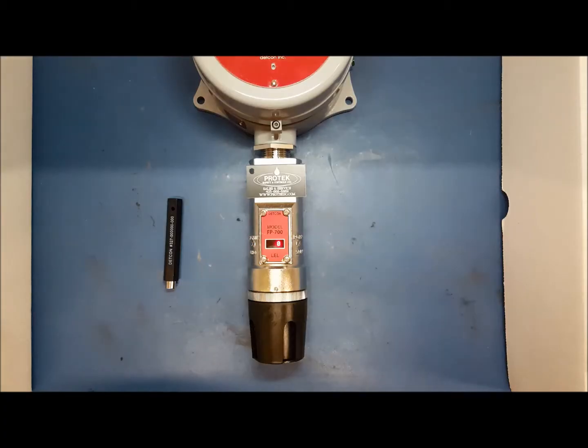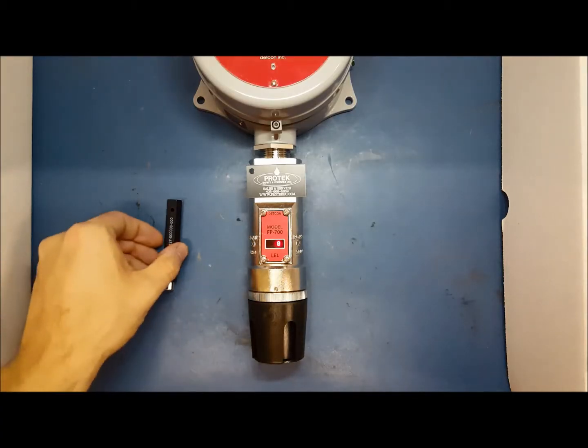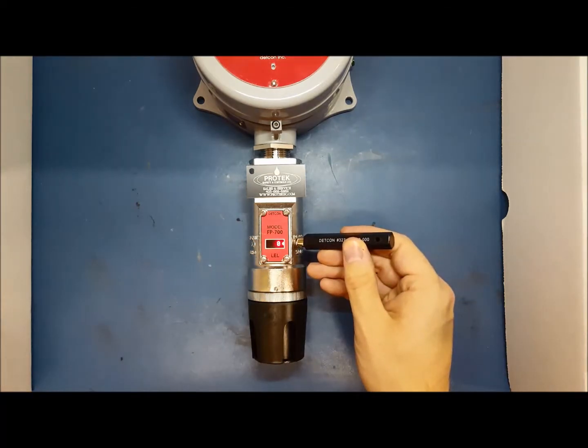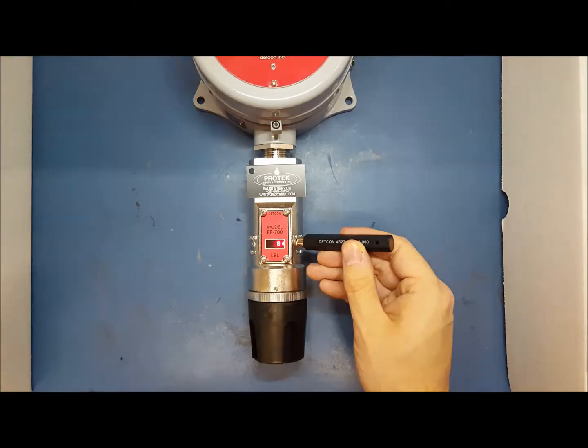With the unit powered up, hold the DETCON programming magnet over PGM2 on the ITM. An arrow will appear on the display pointing right, indicating that the magnet is interacting with PGM2. After 5 seconds, the display will read View Sensor Status across the screen.